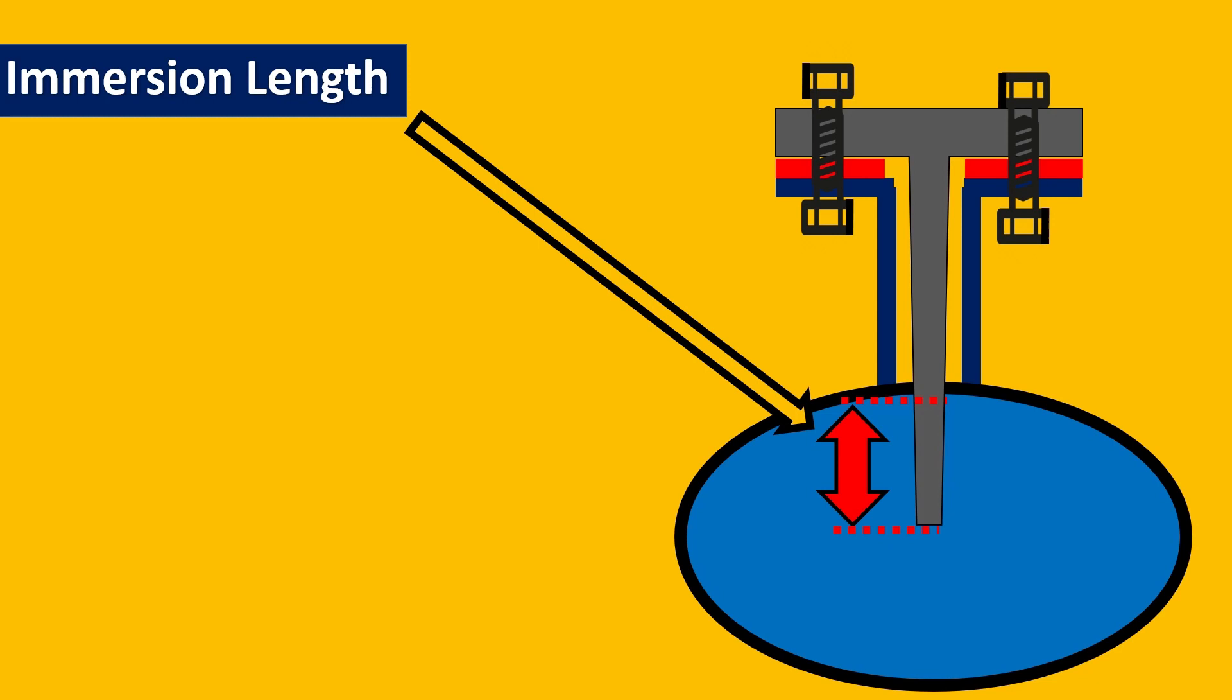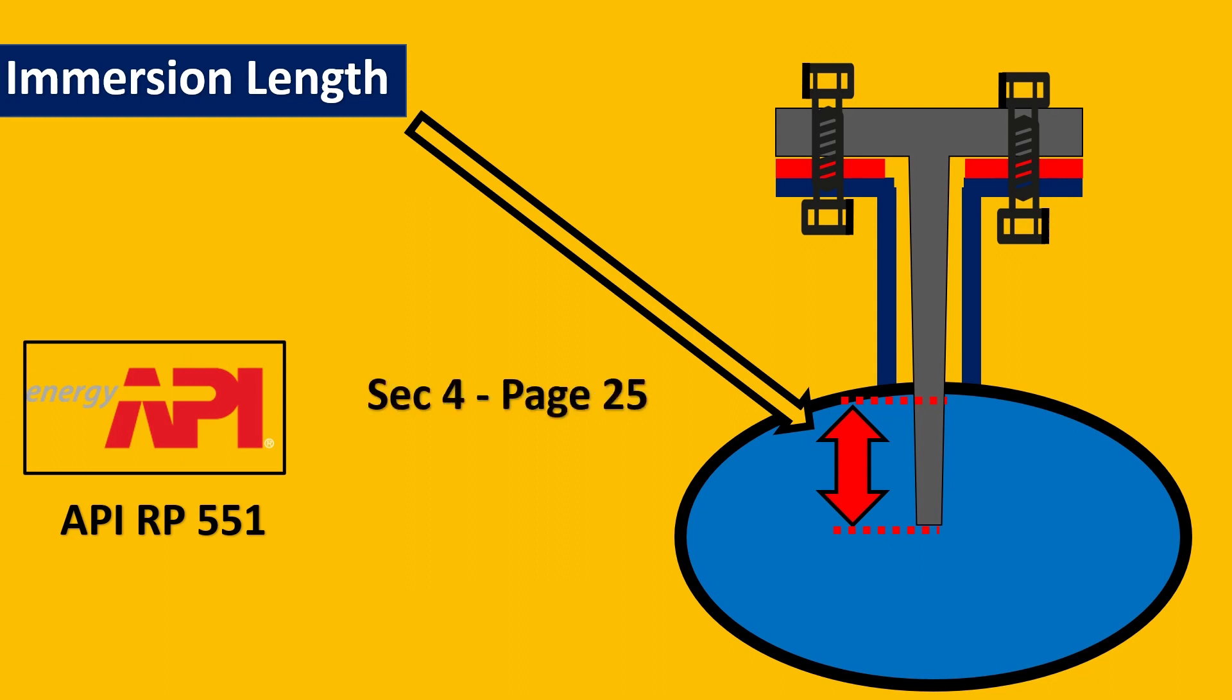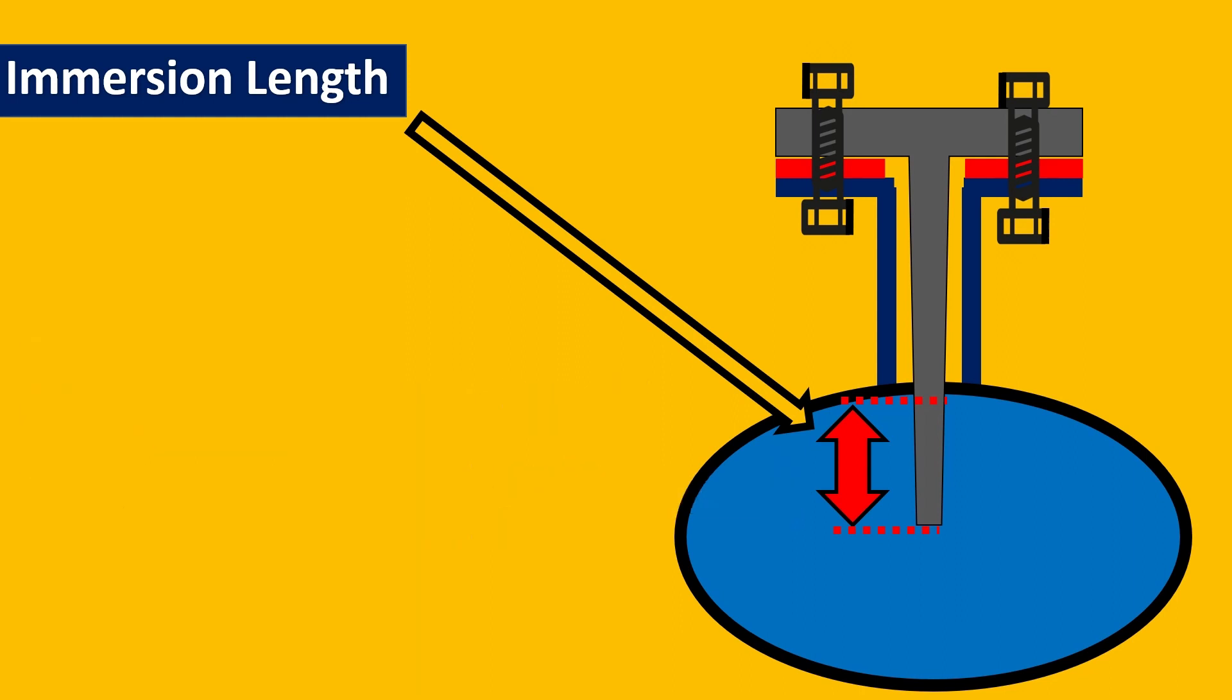This immersion length now has a lot of criteria depending on the standards that you are using, client preferences, etc. We look at some very common or well-known standards and recommendations. So let us go for API RP 551. Here in section 4 and page number 25, it says that the minimum immersion length should be 2 inches, which is around 50 mm. So at least it should be 50 mm within the process if the line is completely filled. Now this is very important criteria. But is it the only criteria? The answer is no.